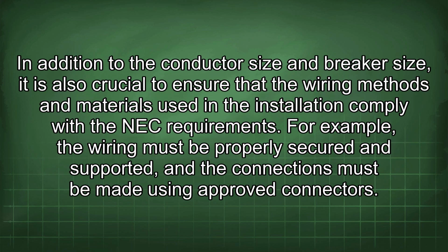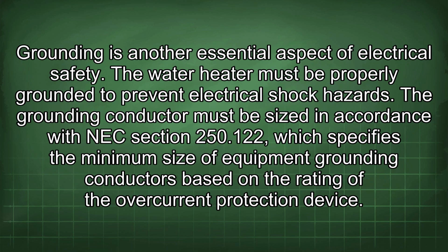In addition to the conductor size and breaker size, it is also crucial to ensure that the wiring methods and materials used in the installation comply with the NEC requirements. For example, the wiring must be properly secured and supported, and the connections must be made using approved connectors. Grounding is another essential aspect of electrical safety. The water heater must be properly grounded to prevent electrical shock hazards. The grounding conductor must be sized in accordance with NEC section 250.122, which specifies the minimum size of equipment grounding conductors based on the rating of the overcurrent protection device.